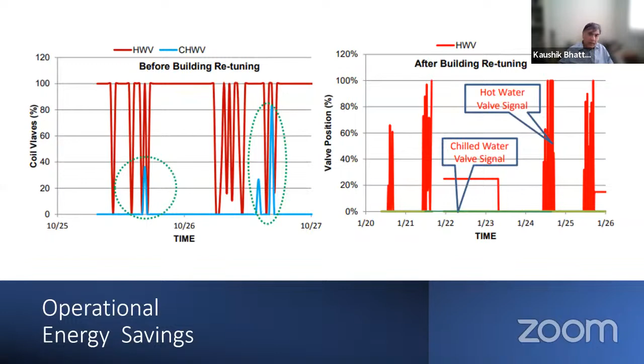As I said earlier, for chillers we need to maintain a big delta T in supply and return temperature. So you can see after performing the recommissioning, the boiler sequence or controls were adjusted in such a way that they could implement a high delta T, or larger delta T, for supplying everything.